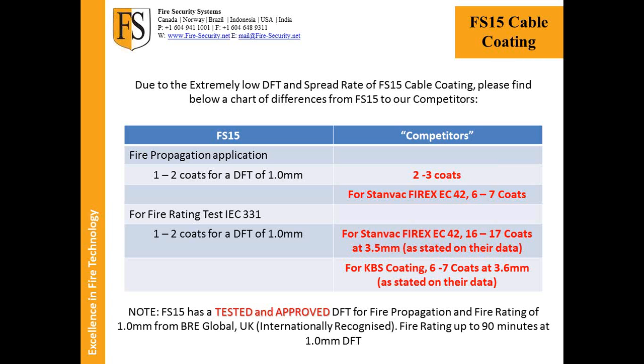So as we discussed earlier, there's two types of approvals. One is just fire propagation, and that is FM's 1.6 millimeter dry film thickness test. That's only applying a coating to stop a spread of flame along a cable surface. There is no time frame for it, there's no hourly ratings, there's nothing. It's just simply a stop spread of flame. The other is for actual fire rating of a cable to continue its integrity, to keep the lights on, the stairwells in a fire, all the signage, machines running, all to get staff out and protect assets. So we look towards those fire rating tests.